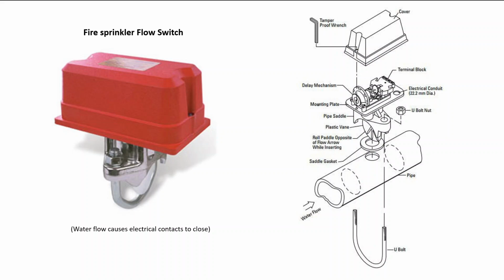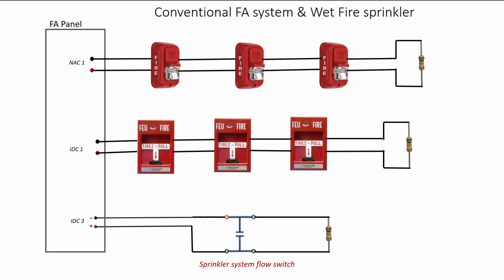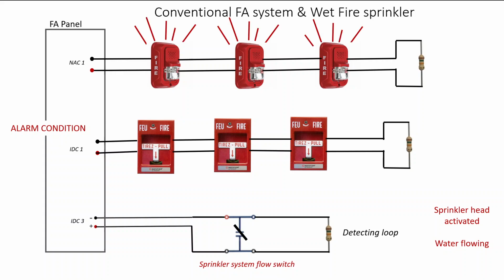Let's see how that's wired to a conventional system. So here we're dealing with a Class B conventional system, and we've got the sprinkler system flow switch down at the very bottom. You'll notice its connection is almost identical to a standard pull station, however it's terminated onto its own separate IDC loop. When the sprinkler head is activated, water starts flowing, and after that 5 to 15 second time delay, the contact should close, at which time we should see an increase in current flowing through this section of my IDC loop, which the fire alarm panel will recognize as an alarm and then flip the notification terminal's polarity to energize all of the NAC devices.